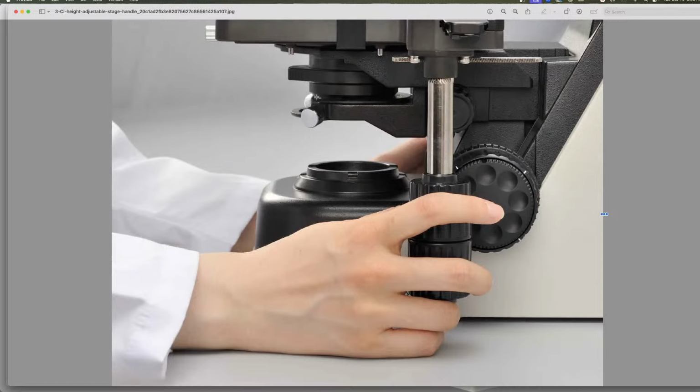It's not Koehler as in C-O-L-A. That would be something completely different. It's Koehler illumination, and it's how microscope lighting needs to be done. The purpose is so that the light you are getting transmitted through your subject and into your eyepieces is even, bright, and glare free right across the entire field. And it gives you the maximum resolution and the best contrast you possibly can.